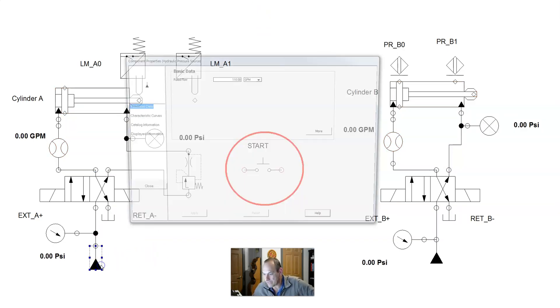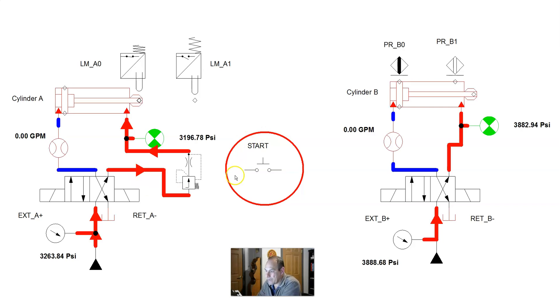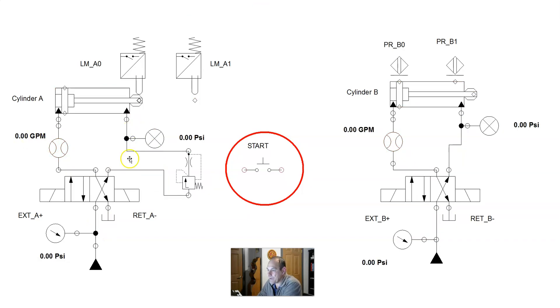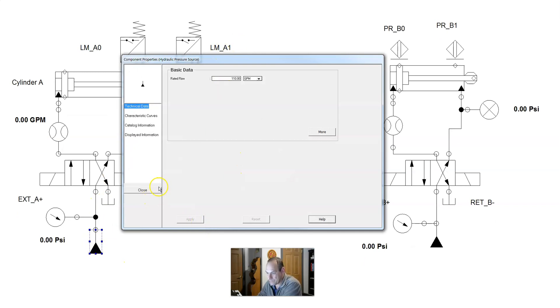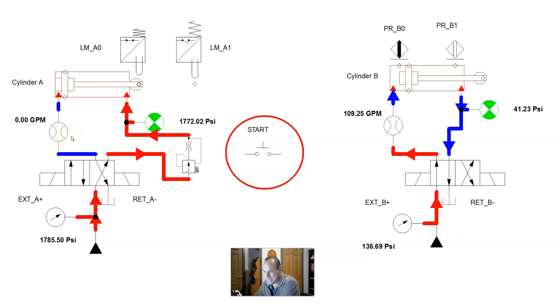Now, what you've seen is I changed the rated flow to 110 gallons per minute. What I wanted to share with you was a couple of basic principles. The hydraulic supply creates flow. So we'll demonstrate this here real quick. Very important principle to understand. We're going to energize our circuit and we're at 107 and three quarters gallons per minute. Now if I bring that down to 20 gallons a minute, let's slow this system down and look at what our flow rate is.